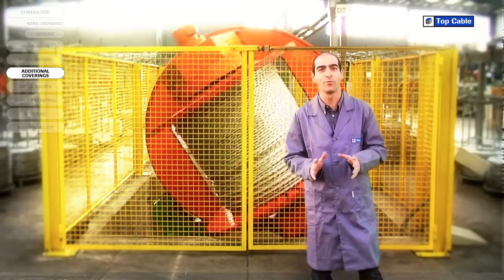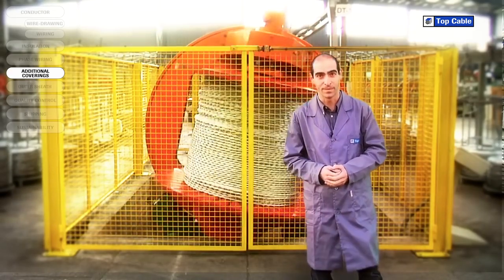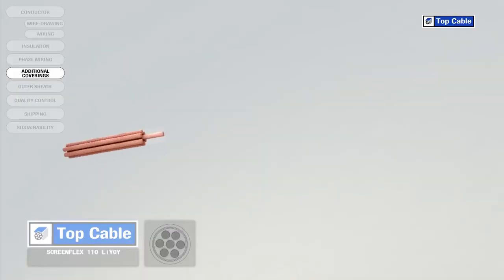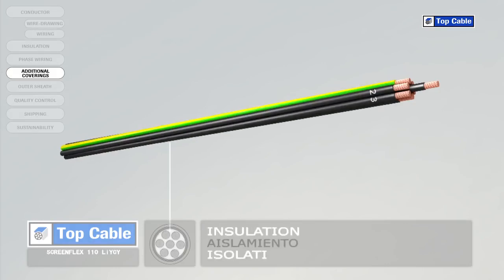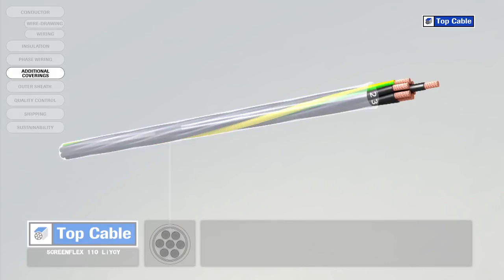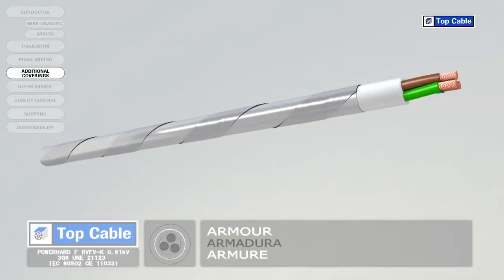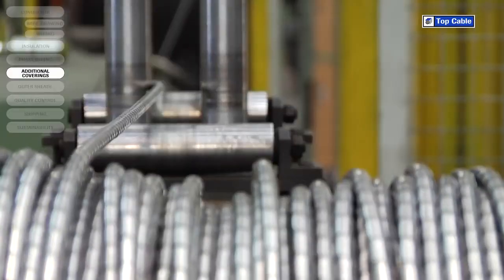In some cases the cable may require additional elements in order to improve its protection or operation. Electrical coverings, also called screens, insulate the signals that circulate in the cable from possible external interference. They also shield the power cables to prevent them from interfering with adjacent signal circuits. Mechanical coverings, also called armor, protect the cable from external damage that may occur from knocks, rodents and any other potential causes. The armor is made from steel or aluminum and can come in the form of metal strips, wires or braids.